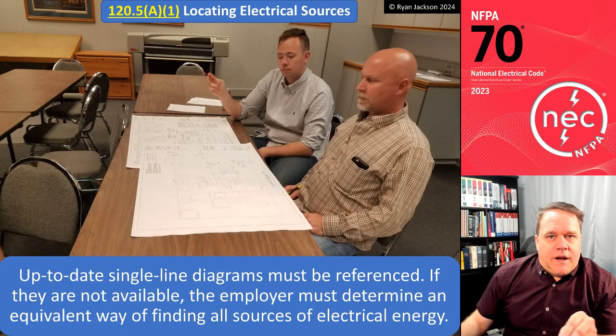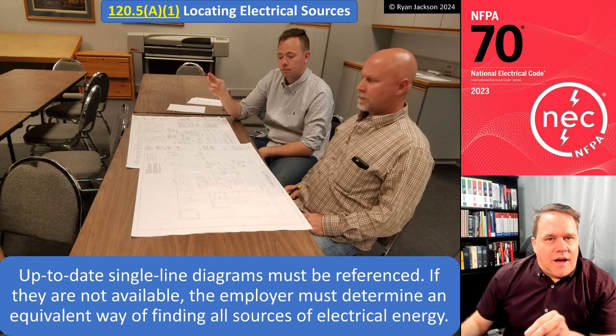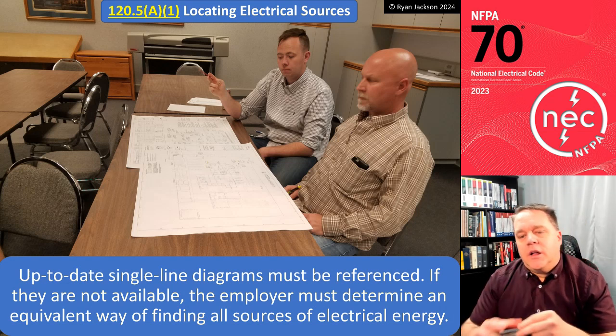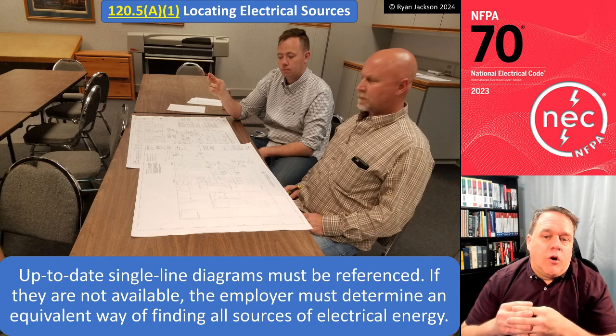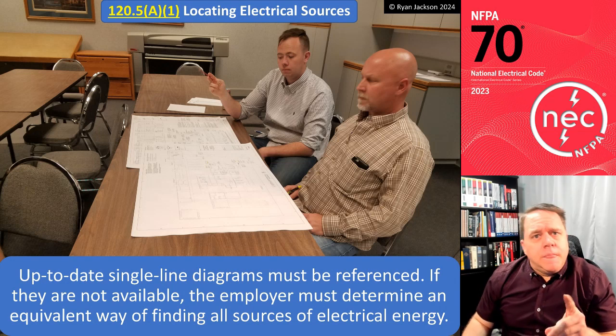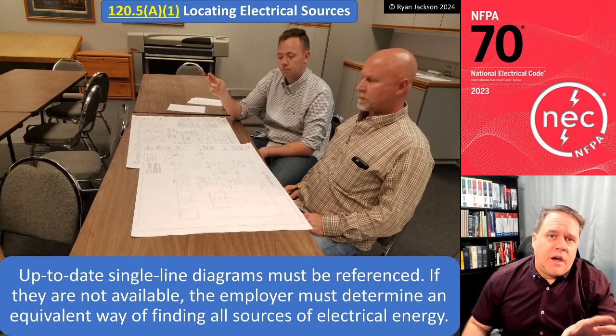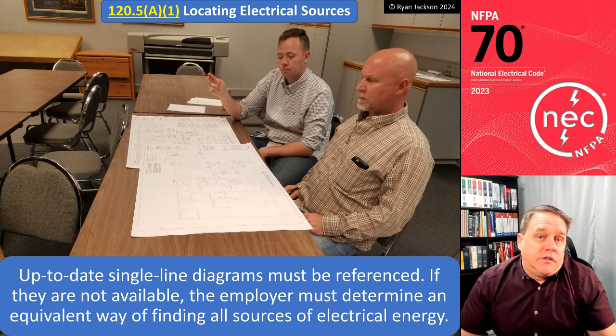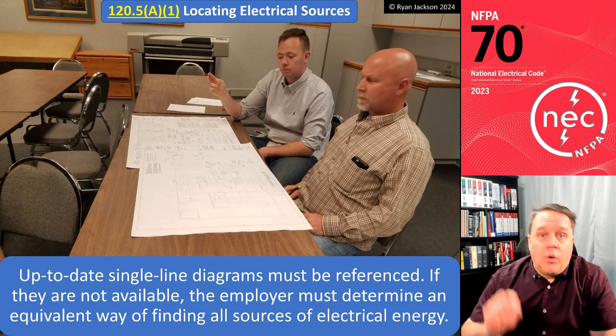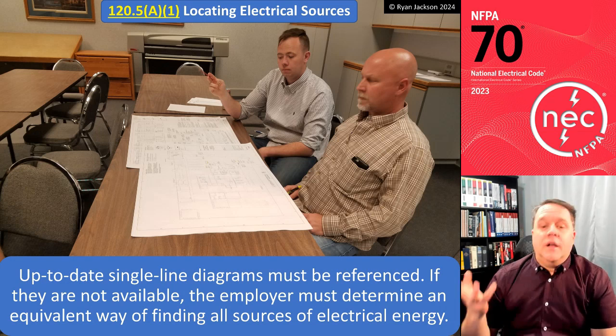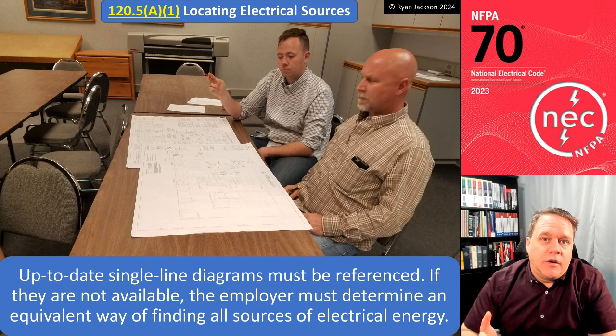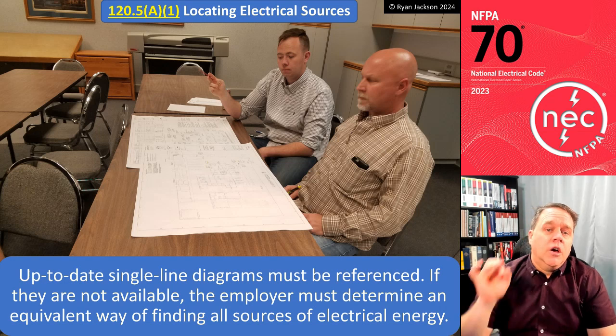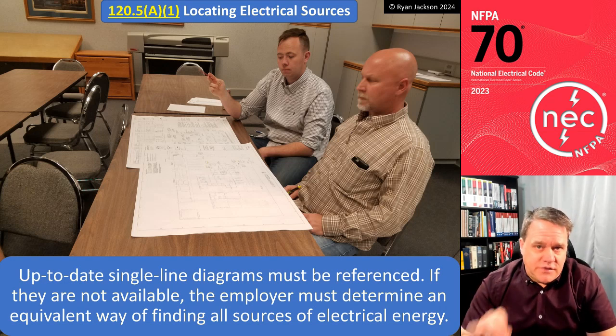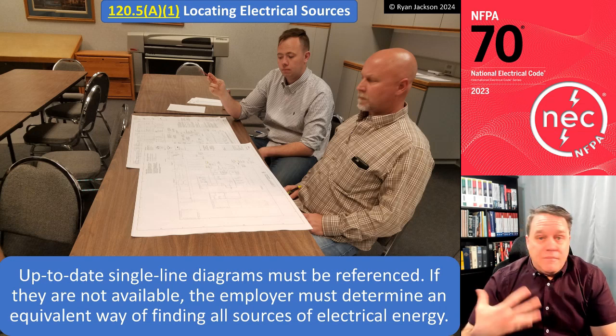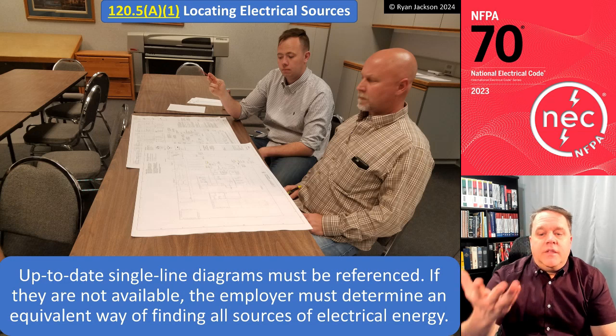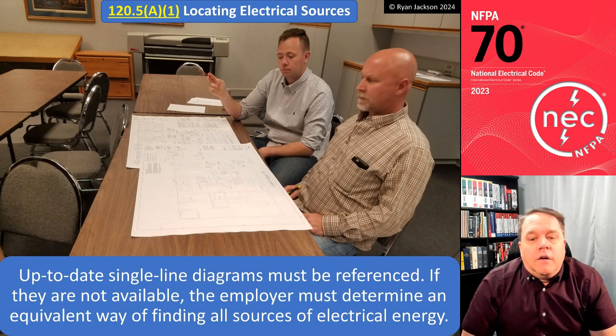Locating the source, 120.5(A)(1). Up-to-date single-line diagrams must be referenced. If they're not available, the employer must determine an equivalent way of finding all sources of electrical energy. This is step one in creating an electrically safe work condition, identifying all sources of electrical energy. And quite frankly, this is usually the most difficult part. Knowing what to shut off is the hard part. So if you have up-to-date single line diagrams, you've got to use them. And again, if you're at a facility, hopefully you have access to up-to-date single line diagrams. If you're a construction electrician, maybe you have them, maybe you don't. If you don't, then the employer needs to determine an equivalent way of finding all sources of energy.